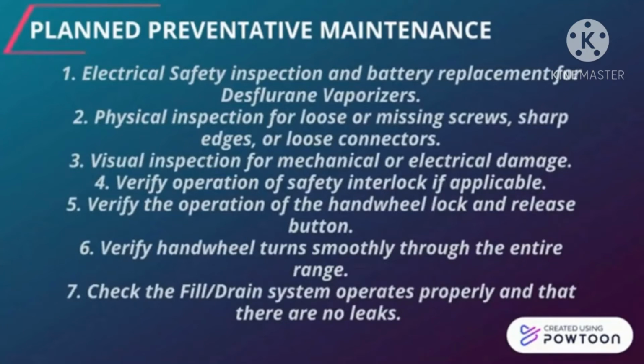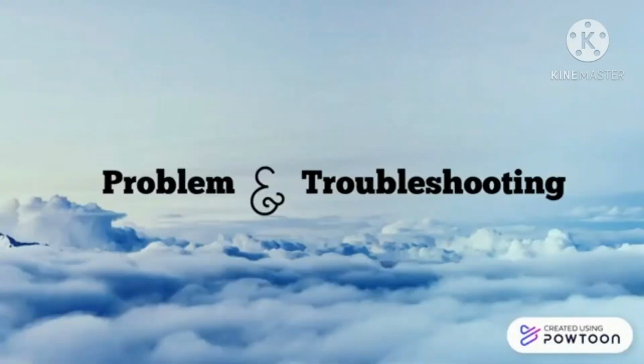Four, verify operation of safety interlock if applicable. Verify operation of handwheel lock and release button. Verify handwheel turns smoothly without binding in entire range. Check Fill/Drain system operates properly and that there are no leaks. Problem and troubleshooting.